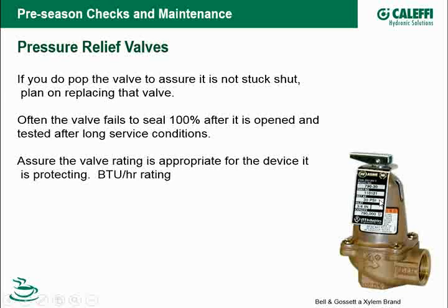You don't know that the last person that might have worked on that or even installed that valve didn't put the right one in. Critical, of course, is the pressure on it, but also the capacity of this valve. You can see in thousands of BTUs per hour. If you've got big commercial systems, make sure you've got a valve big enough to handle the capacity of that system. So these do come in different sizes. They do come in different pressure ratings, and they do come in different capacities down here. So that tag should be on there somewhere, and it's going to tell you what that valve is capable of doing.